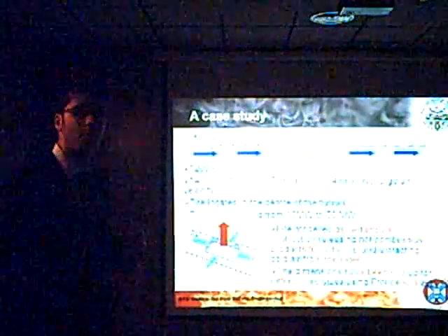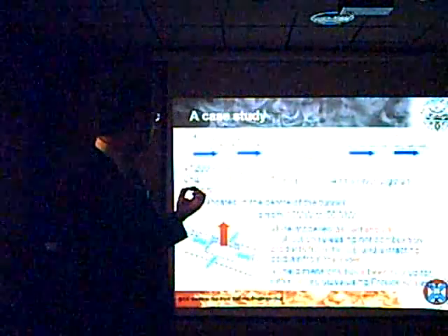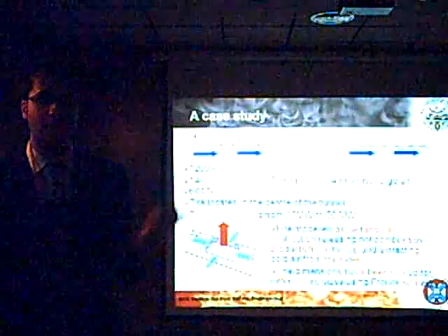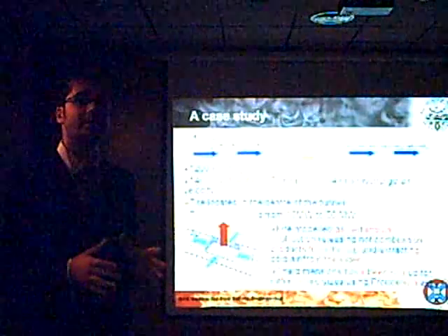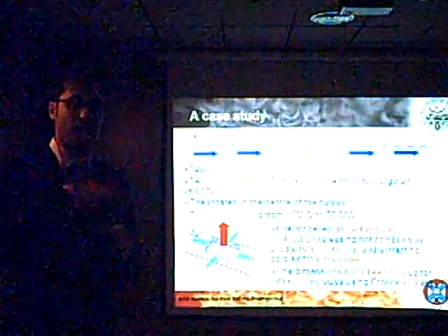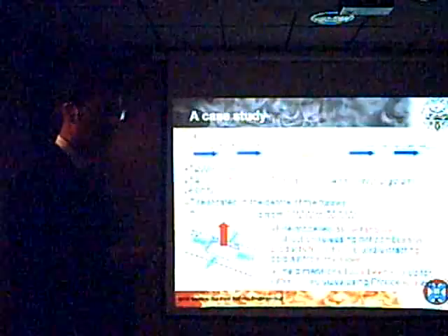What we did is to take a 1.2 kilometer long tunnel that is longitudinally ventilated with 14 pairs of jet fans. They are 15 meters spaced and they have a discharge air velocity of 34 meters per second. And we suppose that the fire is located in the middle, and the fire size ranges from 10 megawatts up to 15 megawatts. In this work the fire has been modeled like a rectangular obstruction in the middle of the tunnel that releases hot gases from the top and entrains cold air from the side. The dimensions of this obstruction have been scaled using Froude scaling.